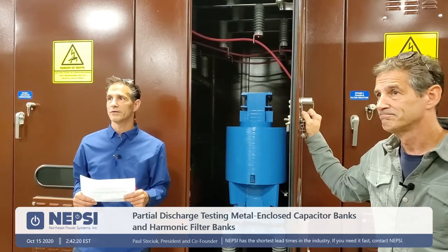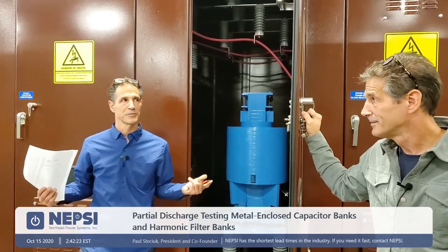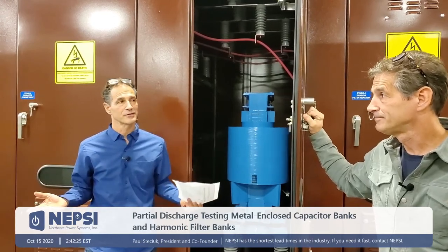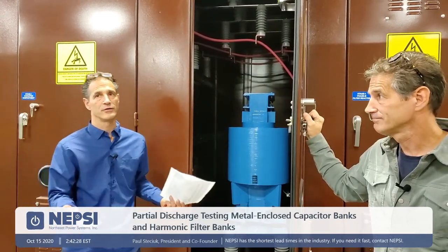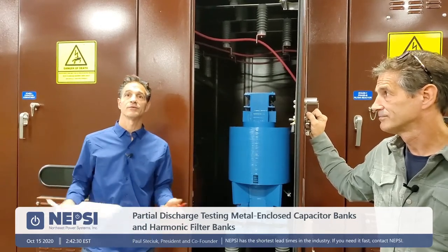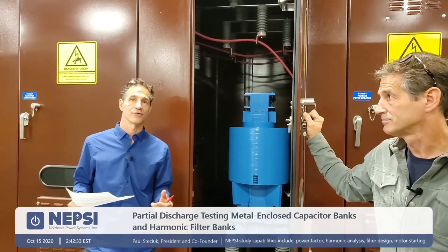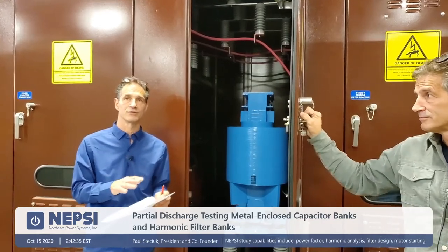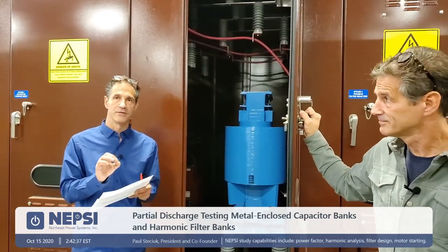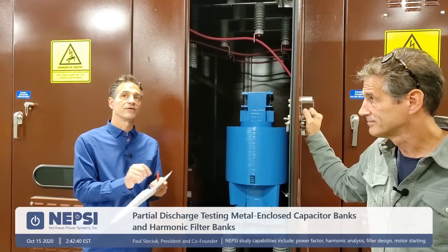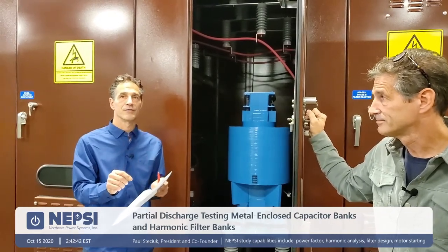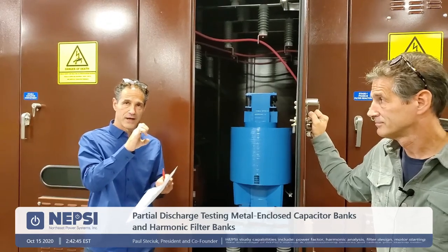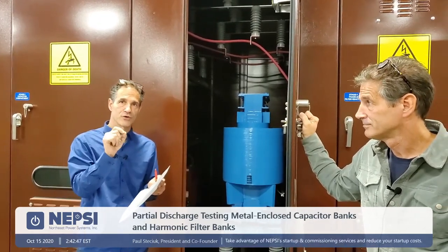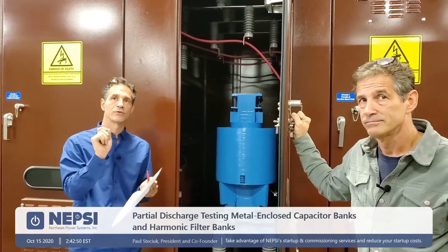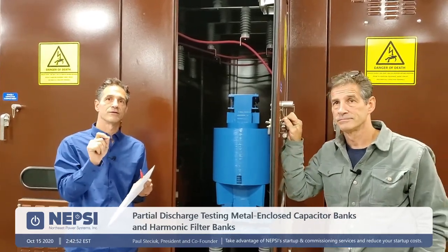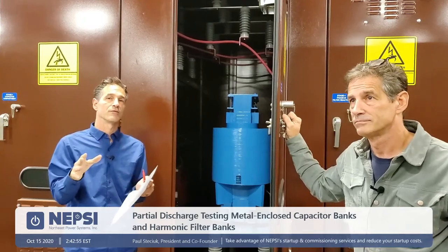Anything else that you might add? No. All right. It's a relatively easy test. You just have to purchase the equipment and learn how to use it, and it will help to guarantee that your equipment lasts 20 years. Remember this about partial discharge testing: it's not an immediate failure that occurs. It's the failure that occurs in time. It's like that Pac-Man analogy, where the discharge is occurring and the insulation is being pounded multiple times a cycle on a continuous basis. It eats away at the insulation and over time it fails.